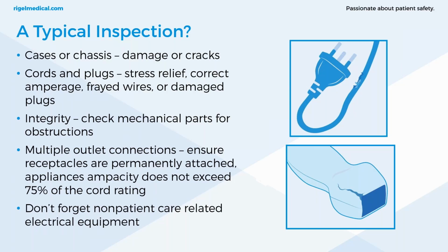One thing to not forget about is that non-patient care related electrical equipment must also be inspected by staff or other personnel. This is not just equipment that's owned by the facility, but also any patient-owned appliances which may be used in that patient area and may come into contact with the patient. So it's not just medical devices, it's also anything that's non-patient care that's brought in, and that is specified in the NFPA 99 code.